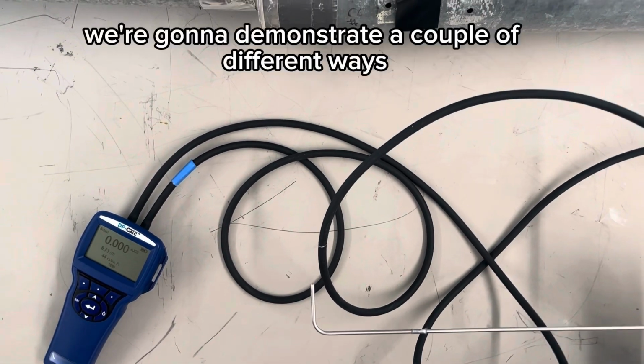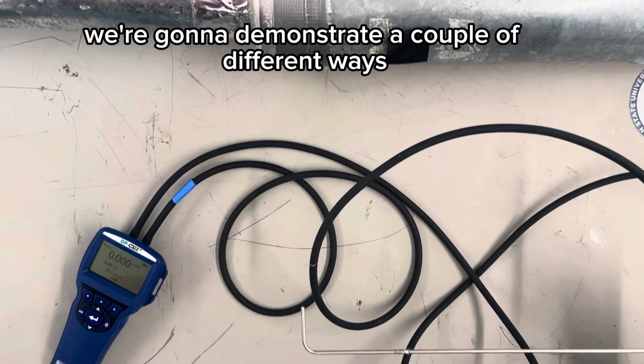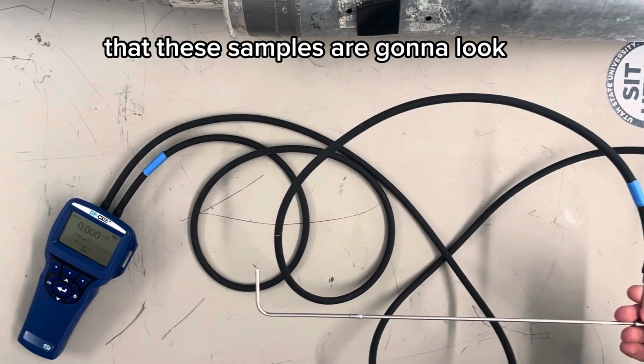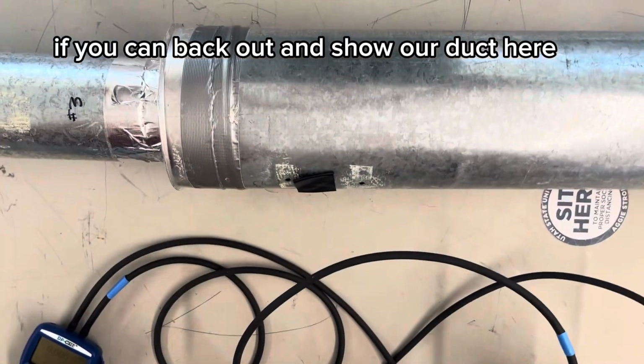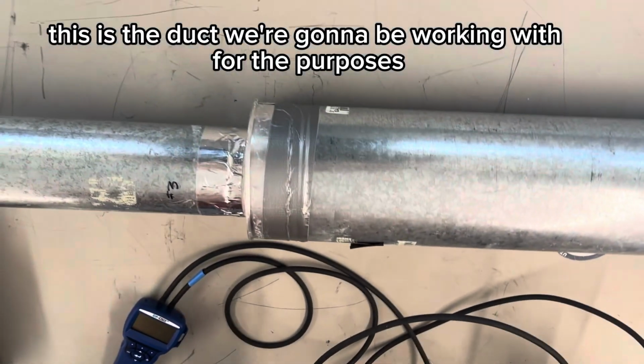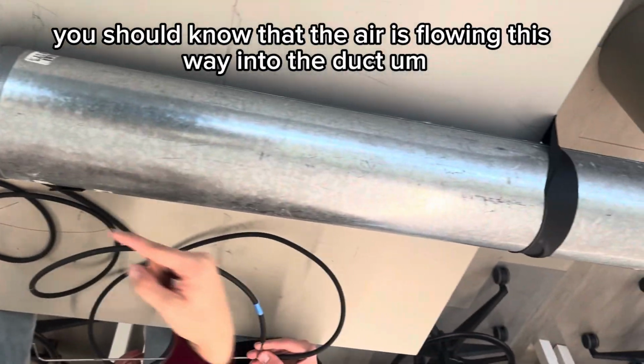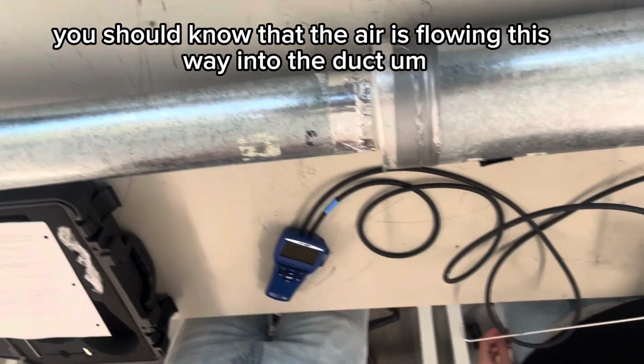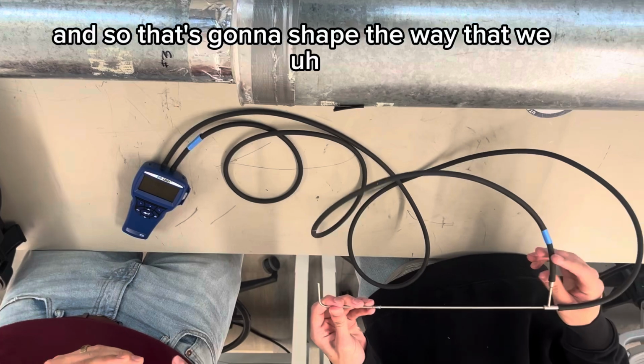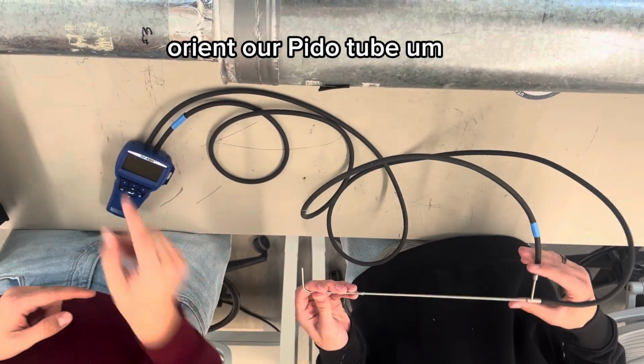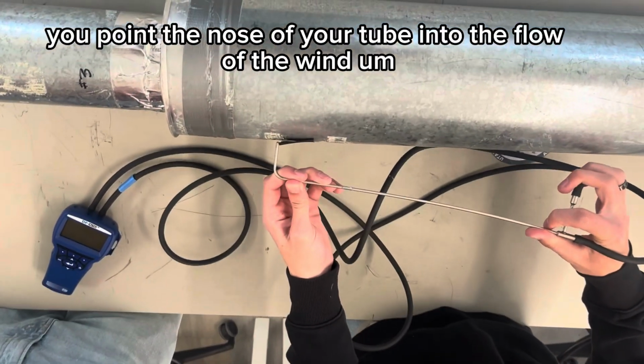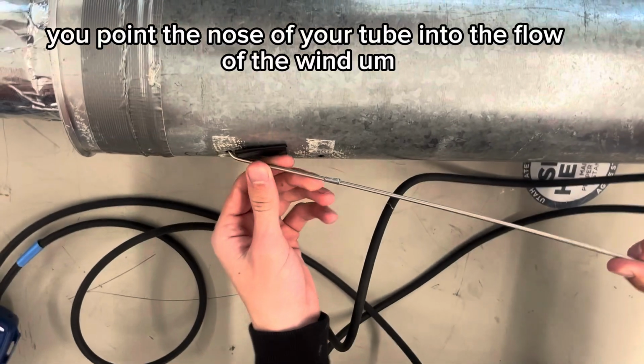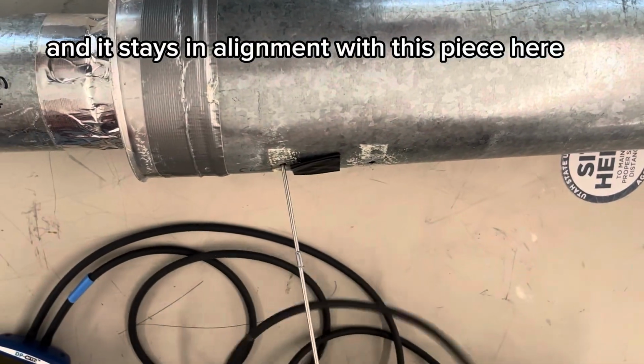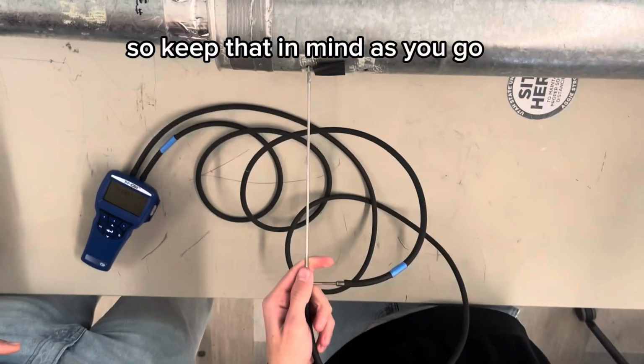All right, so now we're going to demonstrate a couple of different ways that these samples are going to look. If you can back out and show our duct here. This is the duct we're going to be working with. You should know that the air is flowing this way into the duct, and that's going to shape the way that we orient our pitot tube. You point the nose of your tube into the flow of the wind, and it stays in alignment with this piece here. So keep that in mind as you go.